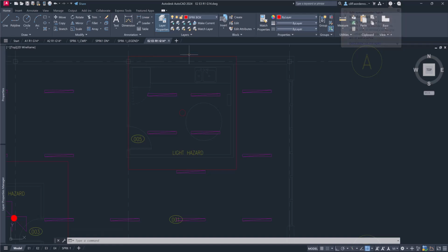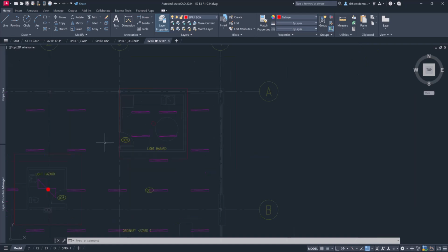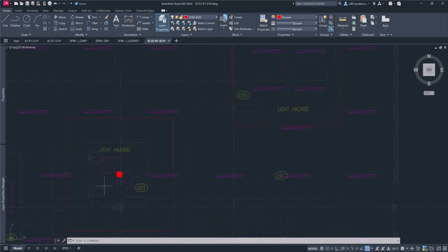All right. You have to make sure that, again, in the space, if the box is on the outside of the walls, this room is perfectly covered by one sprinkler, right? There'll likely be some areas where we might run into trouble. This is another one. Here is a light fixture that's in the way, so this sprinkler is going to have to move ever so slightly.